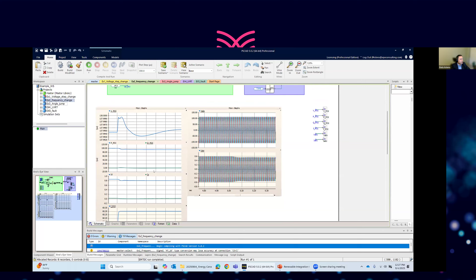We can do the same test for the frequency change. We have the same setup, but this time the frequency goes up just 0.3 hertz. And we can see the jump in the frequency measurement. The expectation is that the power is reduced, which is the frequency response of this IBR, after some delay. There was a question in the Q&A, so you cannot count the inertia as a frequency response. It has a delay in this model.